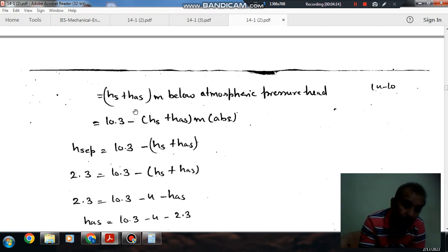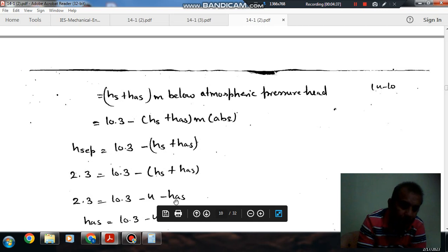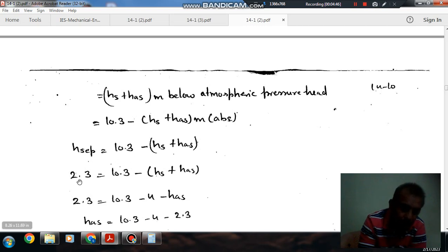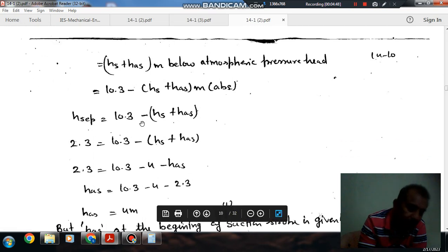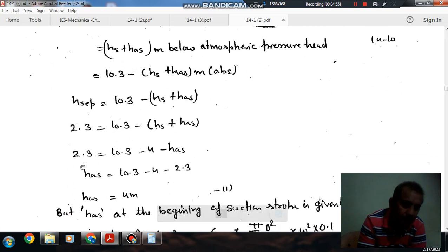And this is below atmosphere head. At the beginning of the stroke, it is 10.3 minus this head because in the suction pipe we have to spend some energy to accelerate the fluid, which will generate some head. So the fluid head at the inlet of the suction stroke will be atmospheric head minus this head. This Hs is given as 4 and Has is unknown. If we want to avoid separation, then this head should not fall below 2.3.